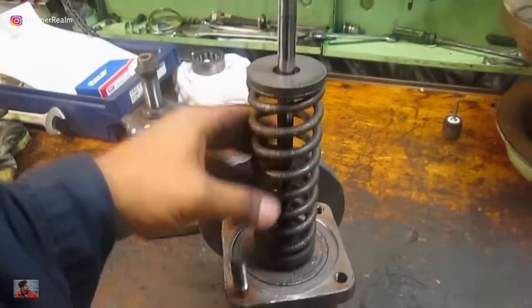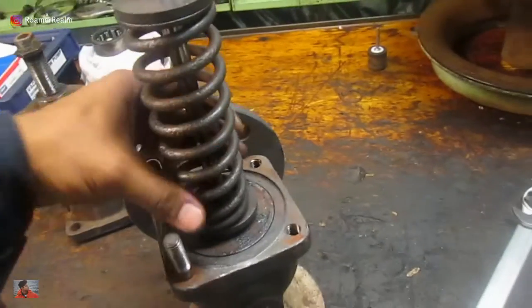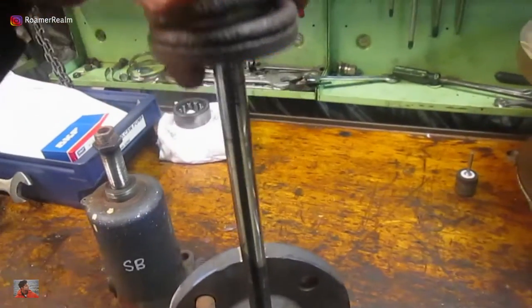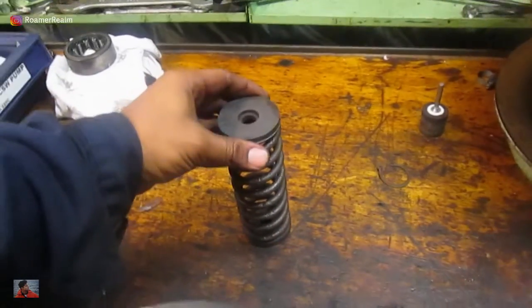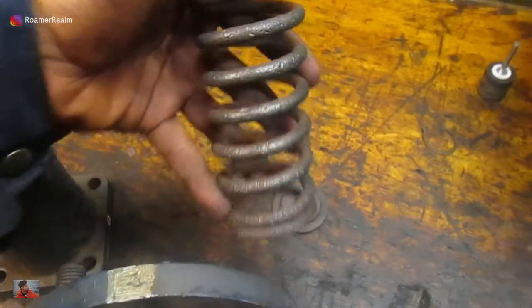The spring has carriers on top and below. This one looks corroded — it's been cleaned up but is still corroded, which shows that there has been water — condensate — going through here. This has already been cleaned.